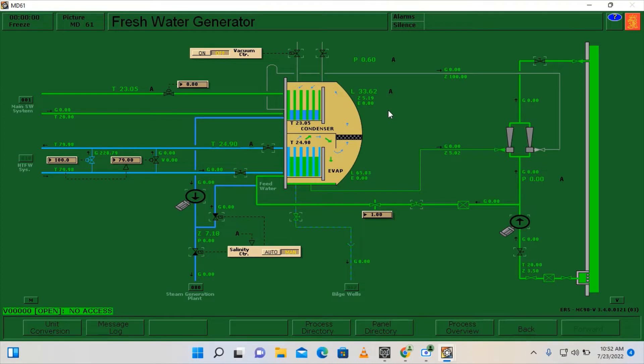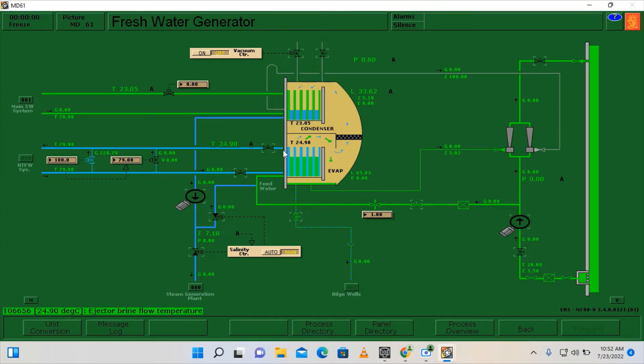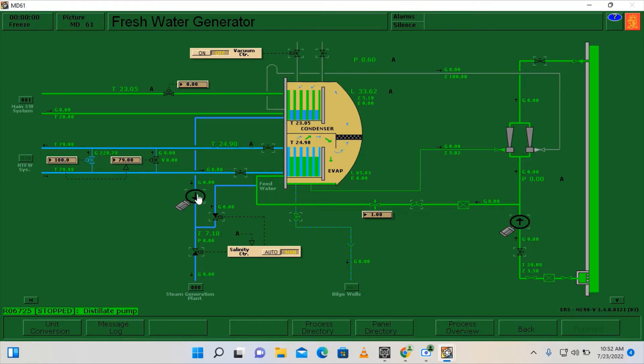As we all know, if we have less pressure inside our fresh water generator then the faster we can boil or create distillate water. We also have here our fresh water generator unit which is mainly composed of the evaporator side and the condenser side. On the evaporator side, this is where the sea water is being boiled and it turns to vapor, and then it will be cooled down here on our condenser.